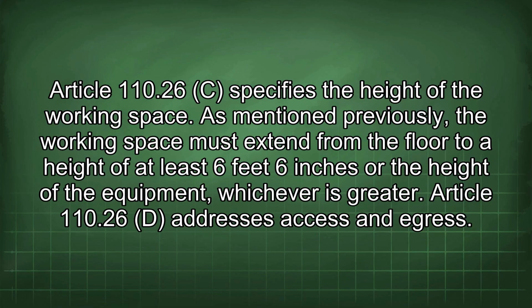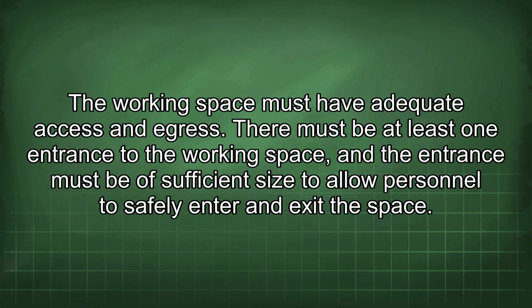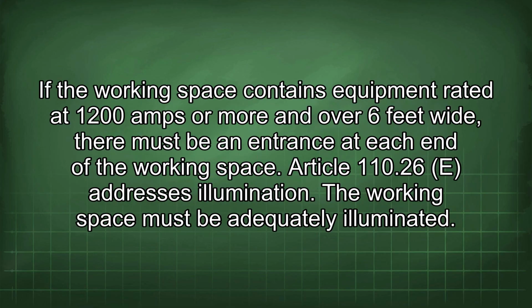Article 110.26d addresses access and egress. The working space must have adequate access and egress. There must be at least one entrance to the working space, and the entrance must be of sufficient size to allow personnel to safely enter and exit the space. If the working space contains equipment rated at 1200 amps or more and over 6 feet wide, there must be an entrance at each end of the working space.